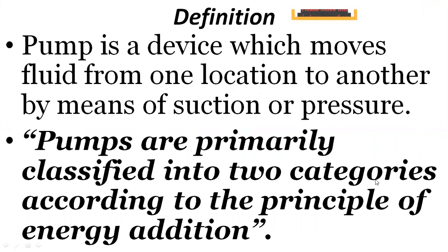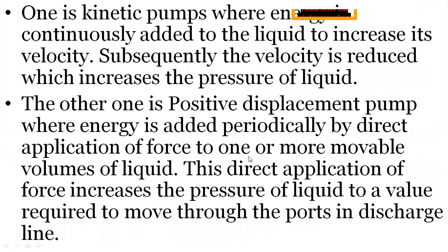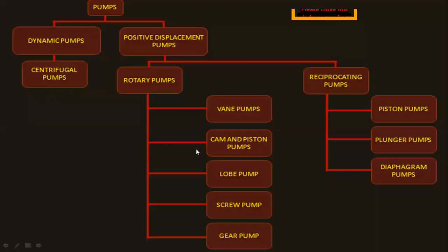Pumps are primarily classified into two categories according to the principle of energy addition. One is kinetic pumps, where energy is continuously added to liquid to increase its velocity; subsequently the velocity is reduced, which increases the pressure of the liquid. The other is positive displacement pumps, where energy is added periodically by direct application of force to one or more movable volumes of liquid, increasing the pressure to move it through the discharge. Kinetic pumps are normally called centrifugal pumps, and positive displacement pumps are called reciprocating pumps.